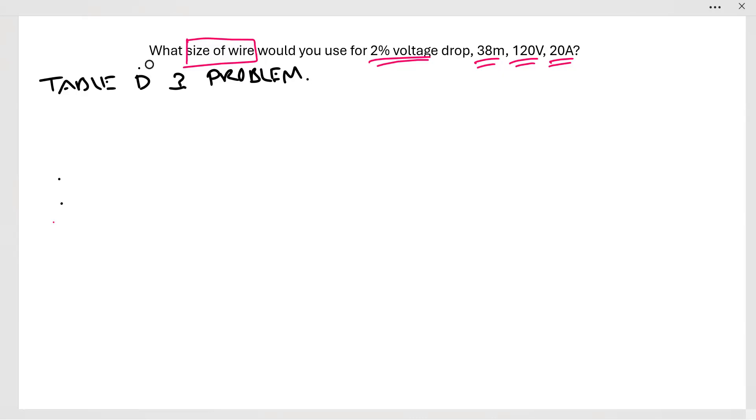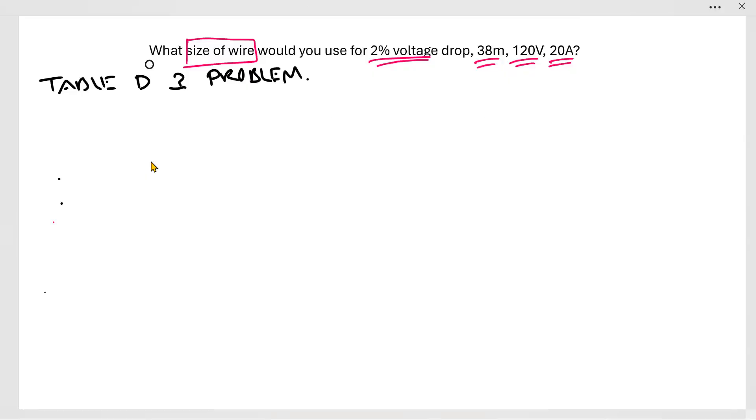From that table, really all the voltage drop calculations that you're going to be doing use the same equation. I like to simplify things and write that equation in a format where we can just solve anything with it. It's not written exactly like this in the code book, but I like to simplify it to exactly this: 1000 meters per kilometer times voltage drop. In the code book they write this various different ways, but really they're just solving for different variables in this same equation. The equation is 1000, which is a conversion between meters and kilometers, times voltage drop equals a K value.